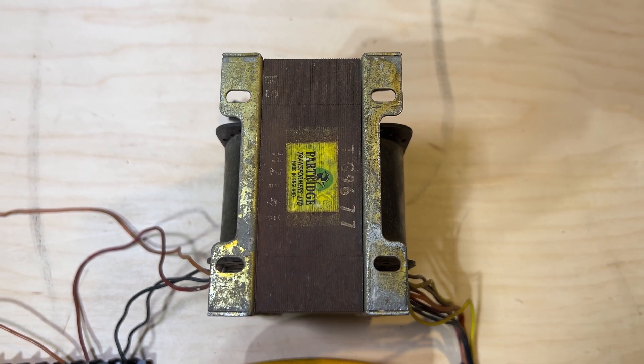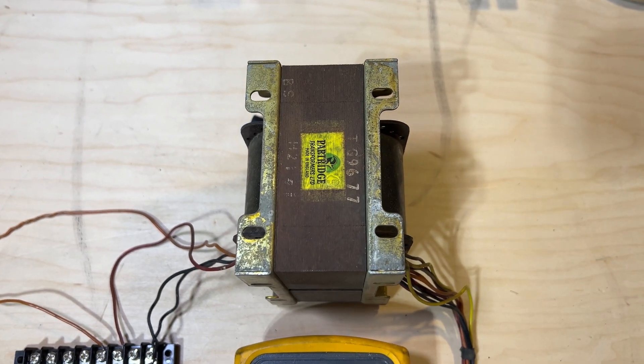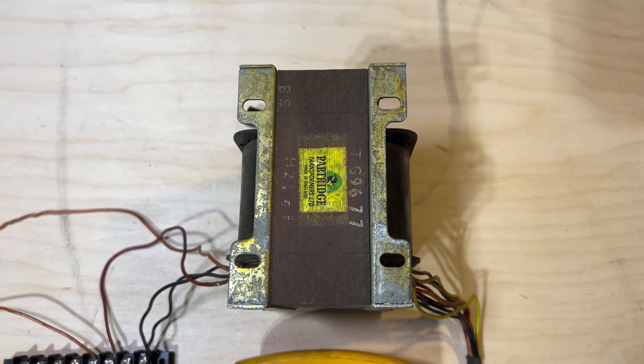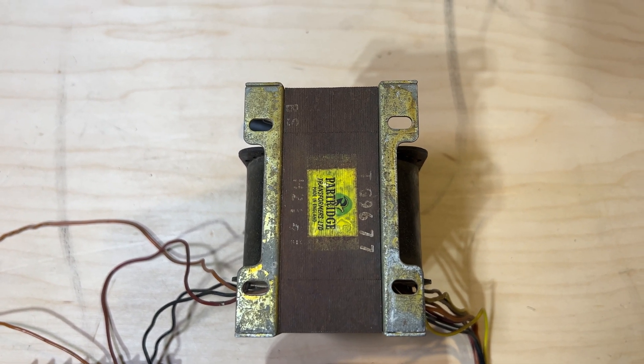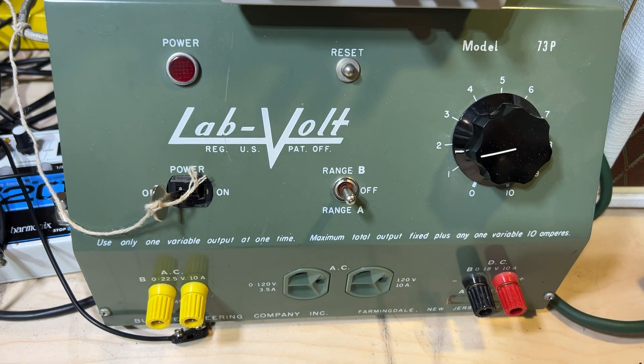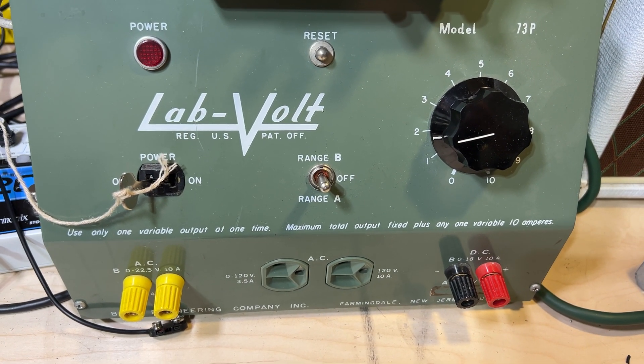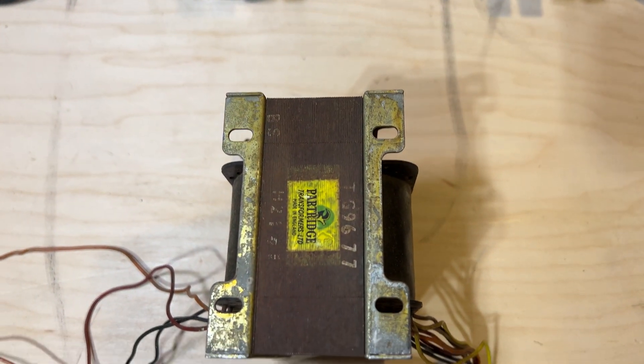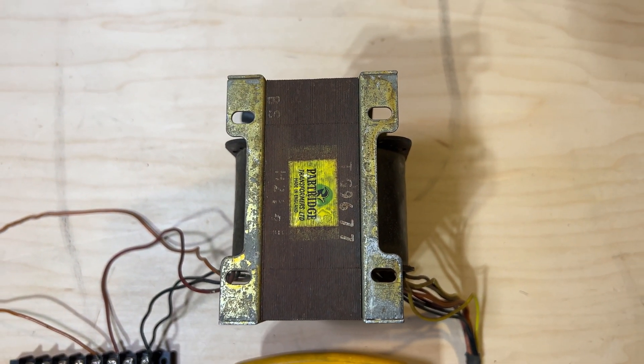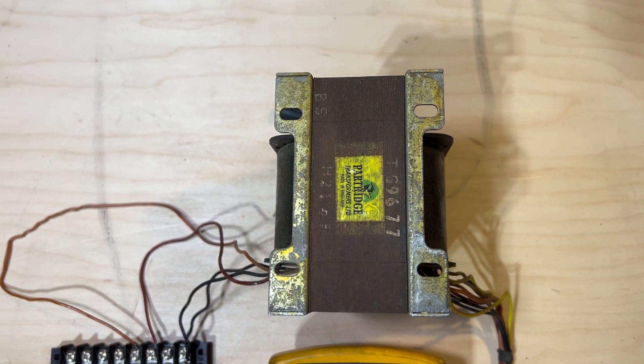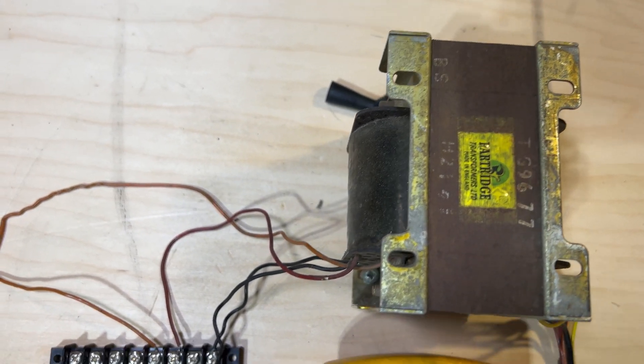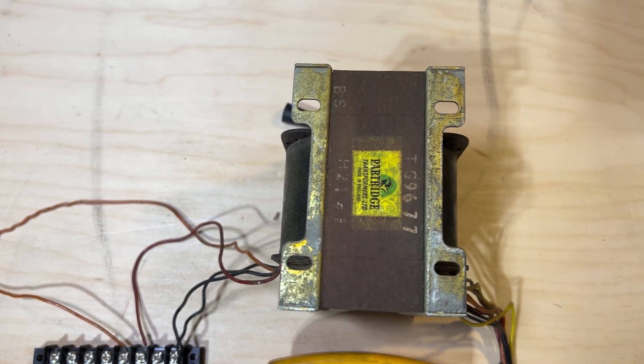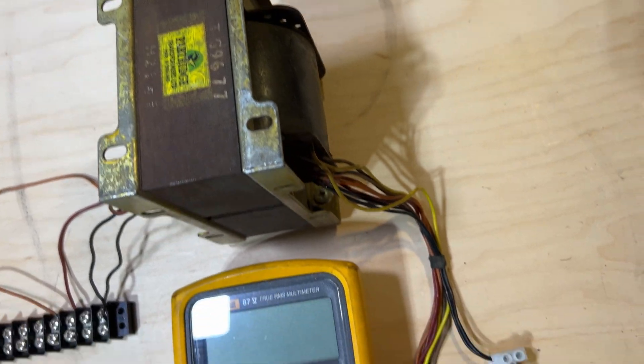We're going to test it out. We're going to do a couple basic tests. I'm going to show you how to do the most basic tests with just measuring resistance, and then also we're going to plug into my Variac, the lab volt, and apply some voltage across this thing to figure out our turns ratio. See if we can kind of confirm through some math what our actual primary impedance is to see if it matches up with what it should be.